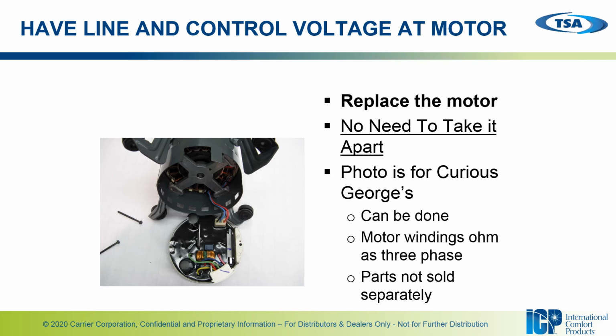So what do you do if you have the line voltage and control voltage at the motor? Simple. Replace the motor. It's a one-piece assembly. No need to take it apart and check whether it's the motor or the module, because you're going to be replacing them both anyway. But here we have a photo for all you curious Georges out there who love to see the insides of mechanical parts. The motor and module actually can be taken apart in two pieces. However, we sell this motor as a single piece unit.